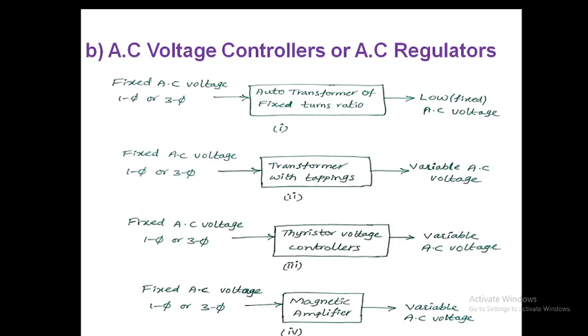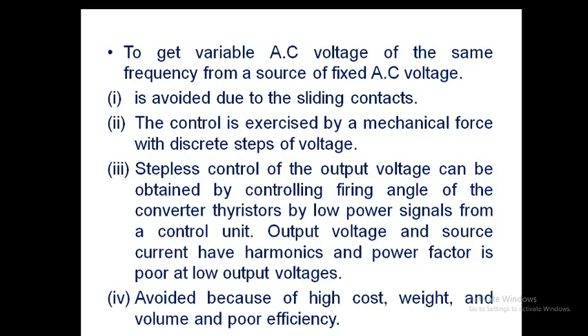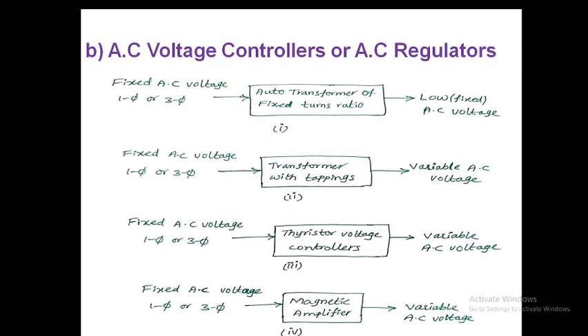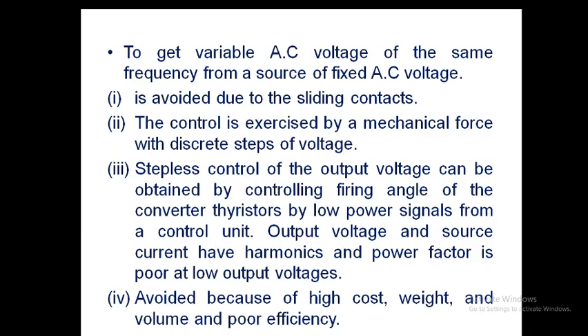Among these methods, some have drawbacks and some have advantages; most of the time we use the third one. The auto transformer is avoided due to sliding contacts, which cause poor efficiency with mechanical involvement. The transformer with tappings involves mechanical force and gives only discrete steps of output voltage. The thyristor AC voltage controller gives stepless control of output voltage using power semiconductor devices, controlled by low power signals from a control circuit by adjusting the firing angle.